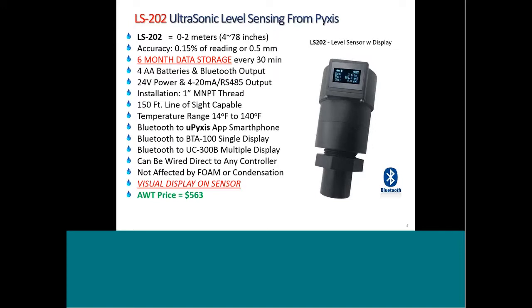In essence, there's a photograph here to the right of what the unit looks like. It's a self-contained unit. It's got a 1-inch NPT threaded bottom. It can be threaded into the top of any tank. It needs to be installed on a level platform. And it contains conventional ultrasonic technology. There is a difference, however, in the ultrasonic beam of this device. It is a very, very narrow diameter beam, and it has some benefits to its operation in that it tends to be extremely accurate in agitated environments and foaming. It has the ability to actually see through foaming during a fill cycle.